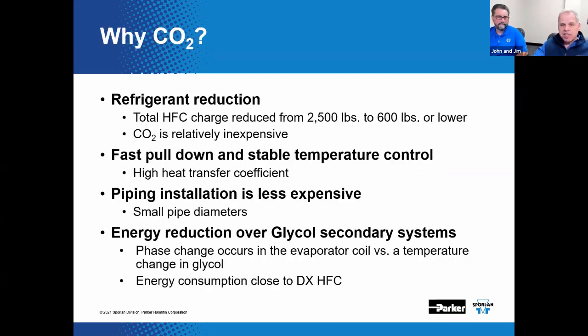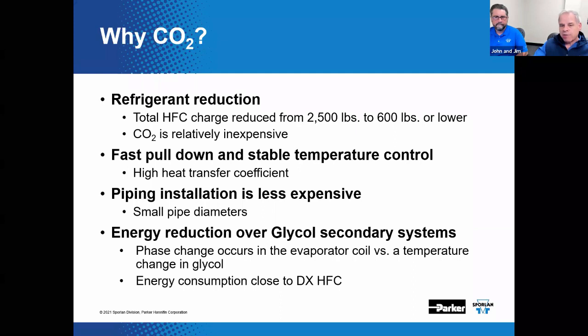Some of the advantages of CO2 liquid overfeed systems are fast pull down and stable temperature control, which is produced by the high heat transfer coefficients of CO2 and having that flooded evaporator. Since the operation at the display case is kind of an on-off via a solenoid valve, this promotes ease of commissioning since only a simple set point is required rather than setting superheat on a lineup of 100 cases with mechanical expansion valves. Correct. I could see that. Correct. There's a lot of flexibility with that liquid overfeed type system. The small pipe diameters are achieved due to the high capacity, which reduces installation time and cost.